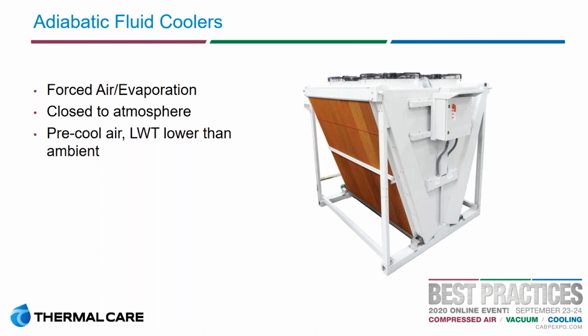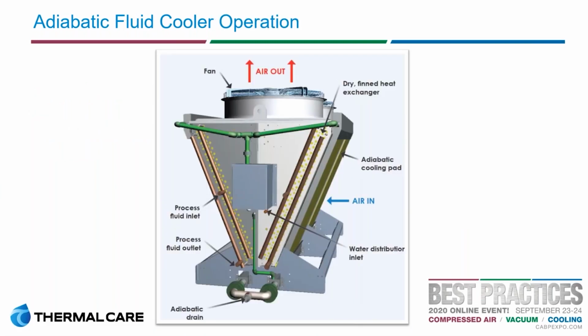When this unit is running, just using forced air based on the ambient temperature, if it cannot achieve its set point, it will release water sprayers at the top that soak that medium on the side. Now as the air is pulled across, it will pre-cool that air. This diagram depicts that a little more clearly. The blue air in is ambient air temperature. If that's too warm to allow us to reach our desired set point, we can use the adiabatic system, depicted with that adiabatic cooling pad. That pad gets soaked, and as the air pulls across it, it pre-cools that air.